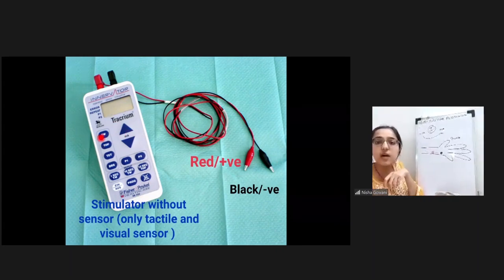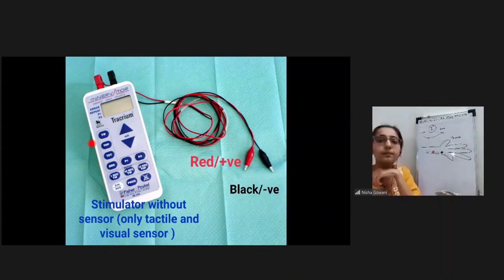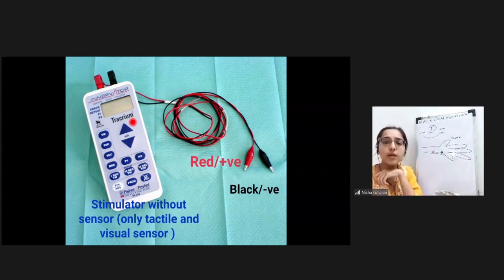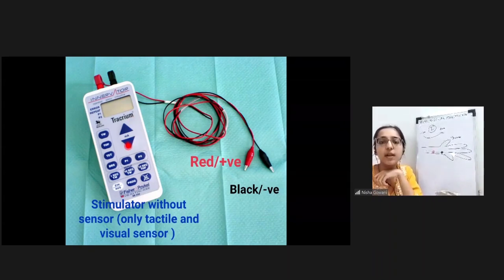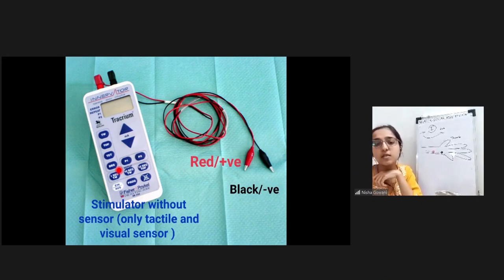On the stimulator, TW stands for single twitch, TOF stands for train of four, TET is for tetanic stimulus, and DBS is for double burst stimulus. In the center, milliampere is mentioned so you can choose the current, going up or down.